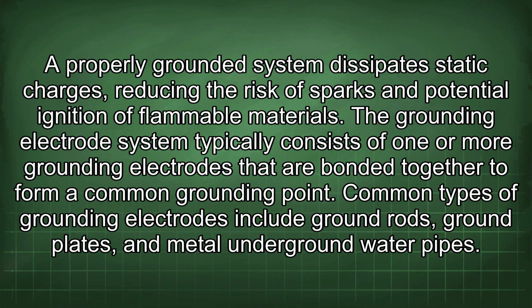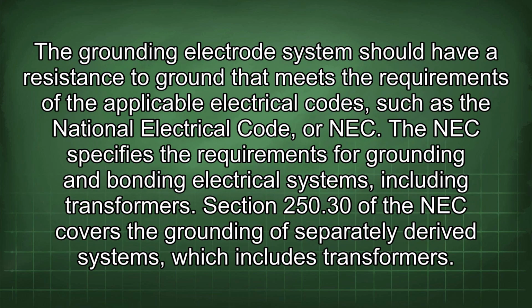The grounding electrode system typically consists of one or more grounding electrodes that are bonded together to form a common grounding point. Common types of grounding electrodes include ground rods, ground plates, and metal underground water pipes. The grounding electrode system should have a resistance to ground that meets the requirements of the applicable electrical codes, such as the National Electrical Code, or NEC. The NEC specifies the requirements for grounding and bonding electrical systems, including transformers. Section 250.30 of the NEC covers the grounding of separately derived systems, which includes transformers.